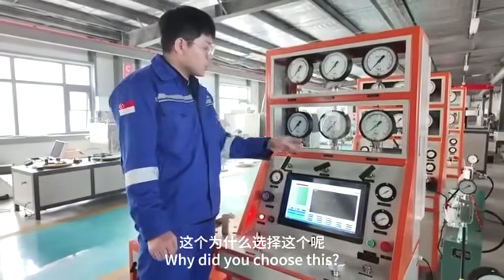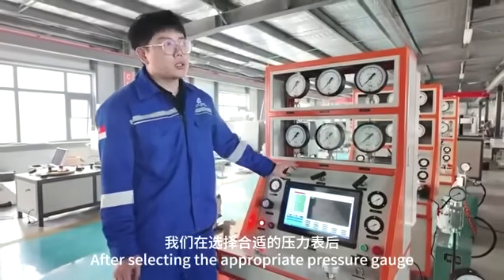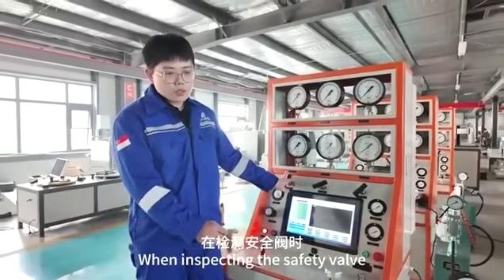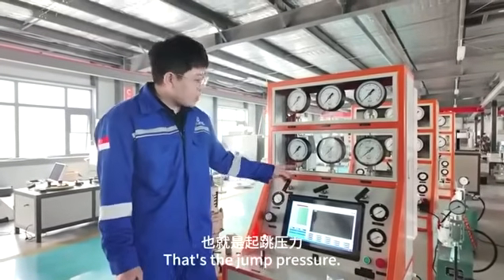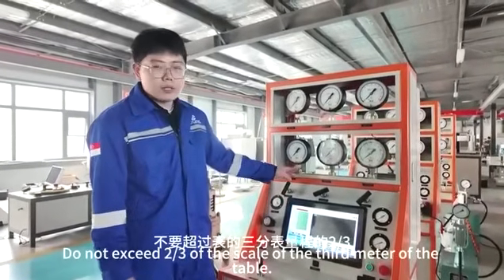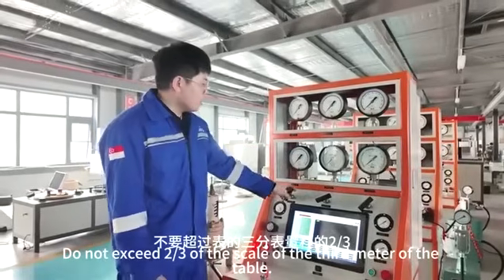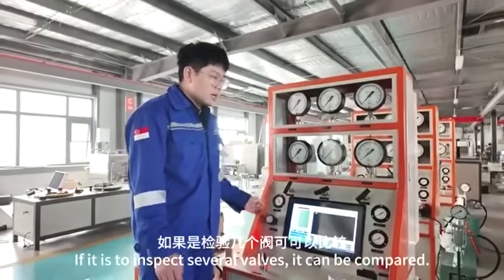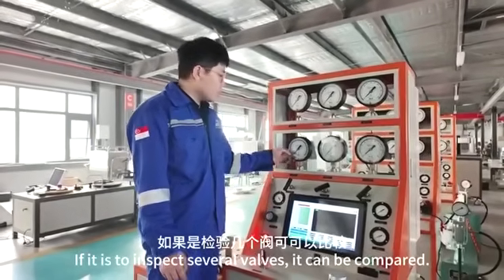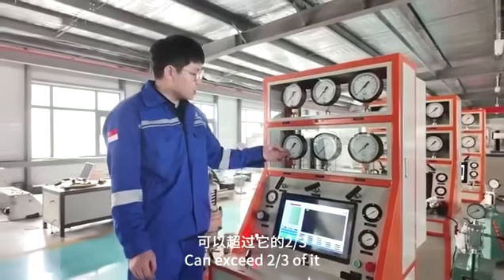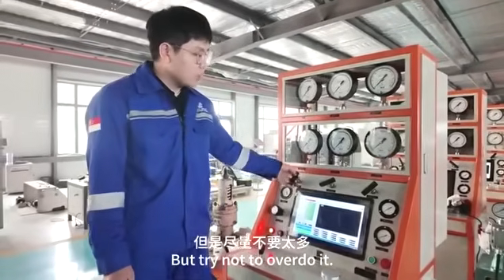Why did you choose this? After selecting the appropriate pressure gauge, when inspecting the safety valve, its setting pressure, that's the jump pressure, should not exceed 2/3 of the scale of the gauge. If inspecting several valves, it can be compared, and can exceed 2/3 of it. But try not to overdo it.